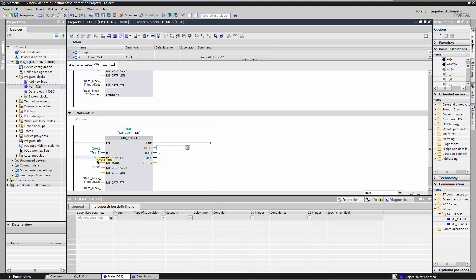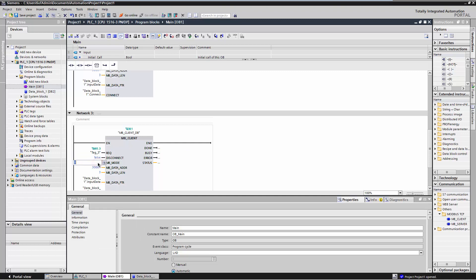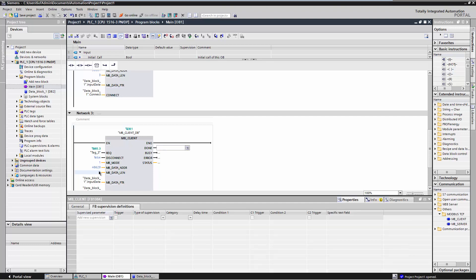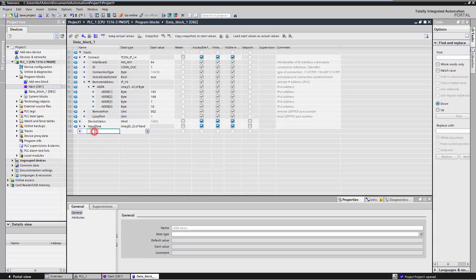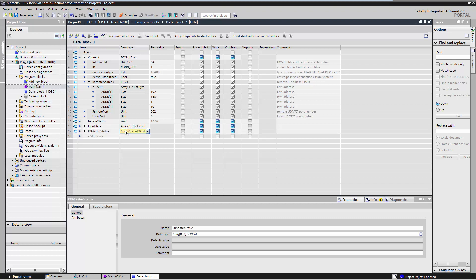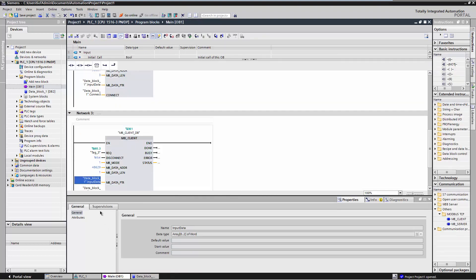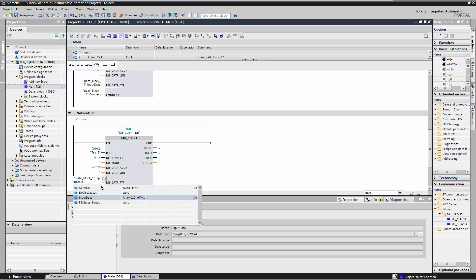To write data, MB_Mode must be set to 1. The status for the Profibus master of the segment PA1 is mapped to the relative holding register 8628. In the TIA Portal, you must enter 48629. The number of registers is 1. In the global data block, create a variable of type Word in order to write the Profibus master status. Adjust MB_Data_PTR accordingly in the MB Client instruction. Add an instruction to reset the REQ input.